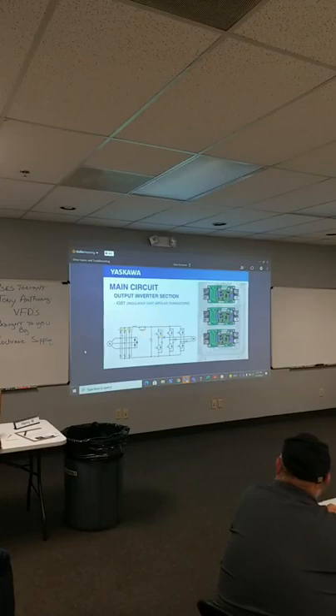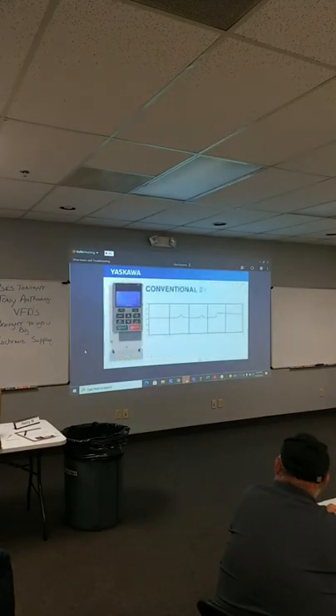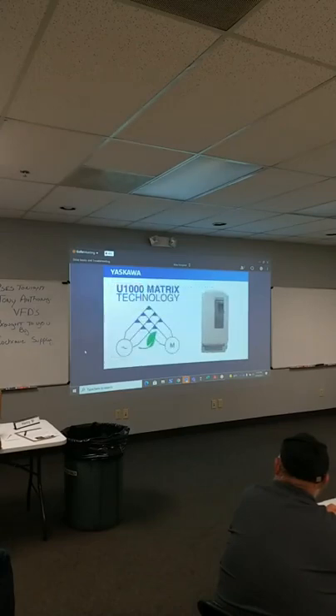However, the rectifier blocks the regenerative energy from flowing back onto the line. This is also one reason why you might encounter an overvoltage trip. Yaskawa does offer systems that have the ability to put power back onto the line. These units use different drive topologies that allow for regeneration.